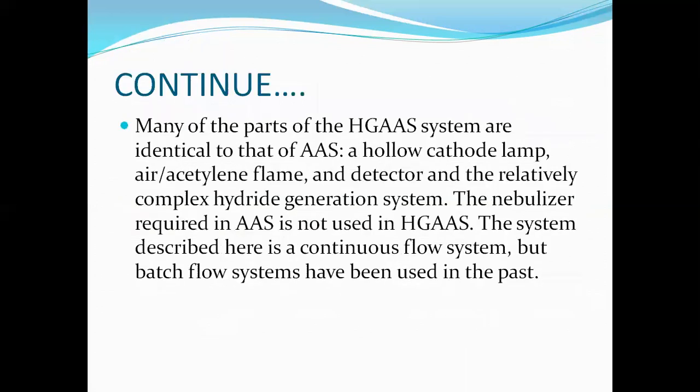Many parts of the hydride generation AAS system are the same as conventional AAS, such as the hollow cathode lamp (radiation source), air-acetylene flame, and detector, along with a relatively complex hydride generation system. The nebulizer required in AAS is not used in HGAAS. The system described here is a continuous flow system, though batch flow systems have also been used in the past.